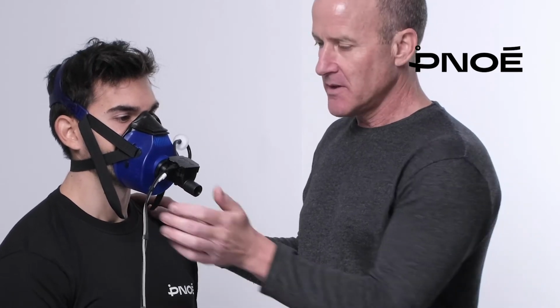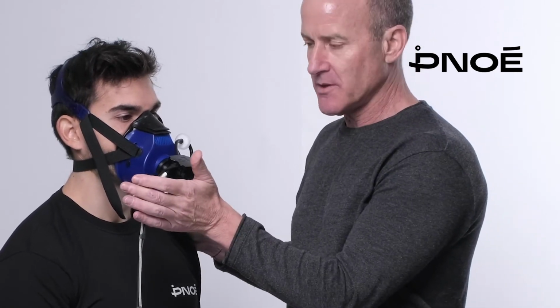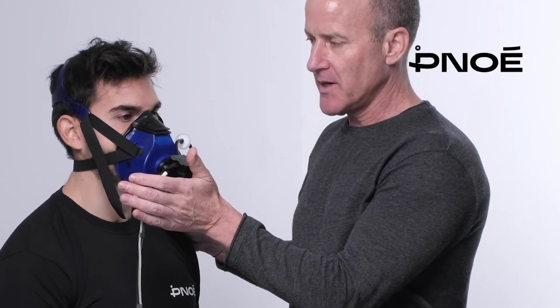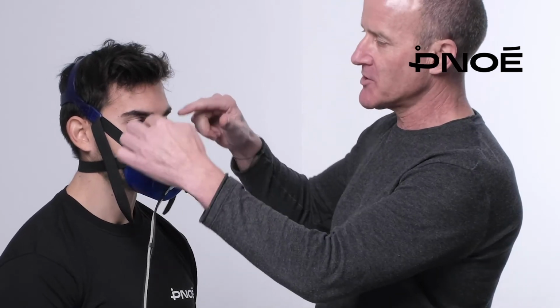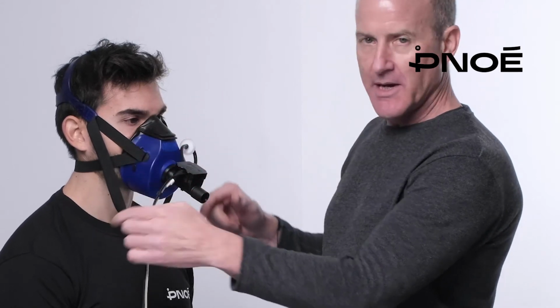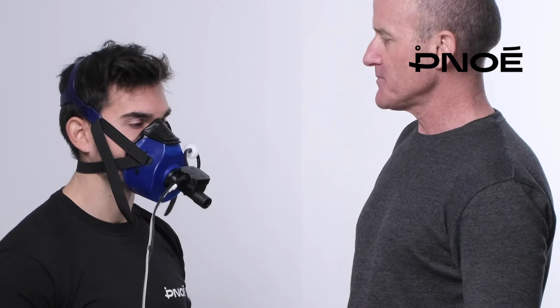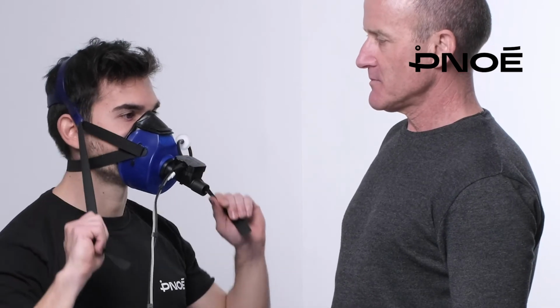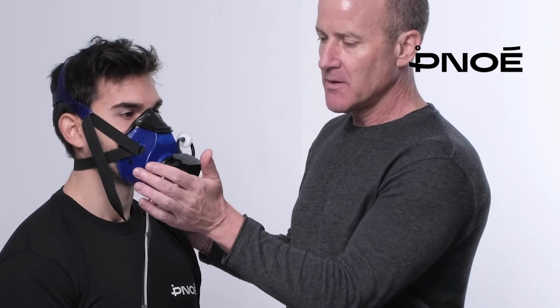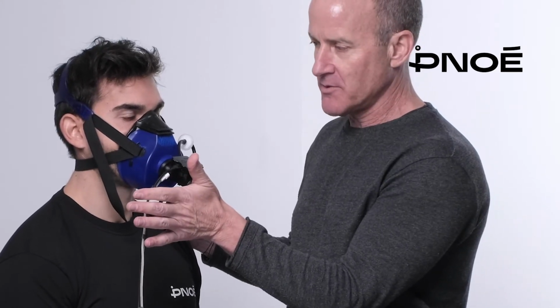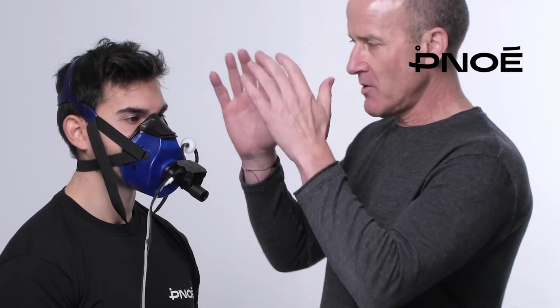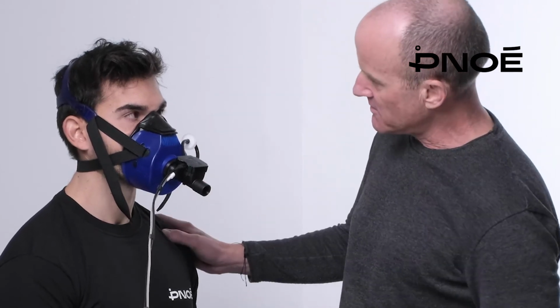And then you could do a seal test. Have them take a breath in and then push pressure out, try and breathe out, and look for any kind of leakage around the mask itself. If they have any leakage, they simply would snug up a little bit more. And then have them take a breath in, block the port, and have them breathe out. And there should be no air escaping around the mask.